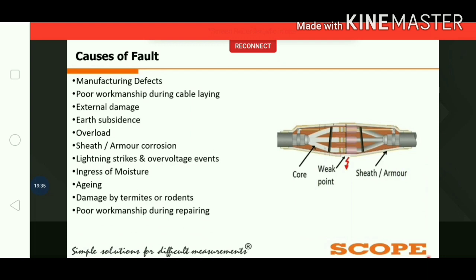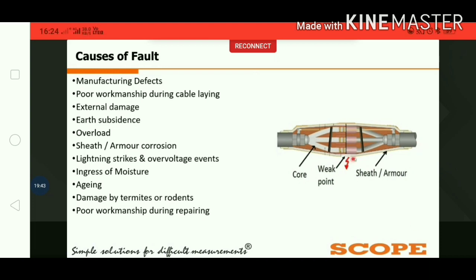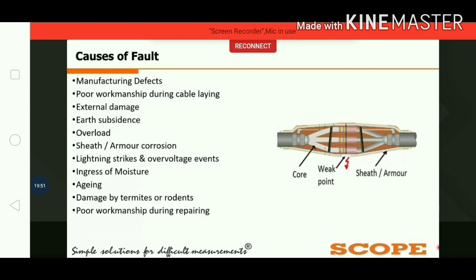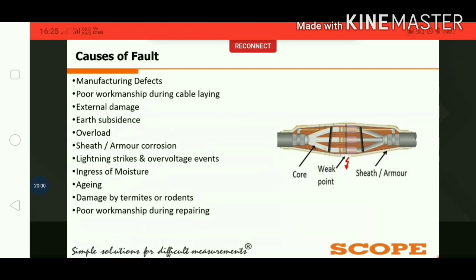The next cause is poor workmanship during repairing. If proper methods or proper care are not taken during repair, faults occur in the cable. As seen in the picture, there is a gap at the joint of the armor, and from this gap moisture can enter the cable, leading to further faults.